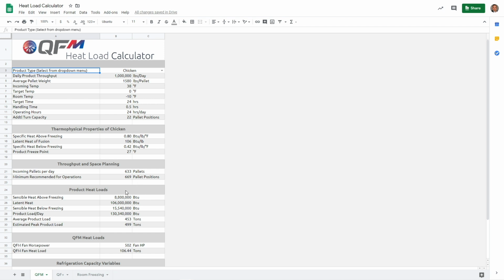We then look at the product heat load. So we have the sensible heat above freezing at 8.8 million BTUs. Our latent heat, 106 million BTUs. Our sensible heat below freezing, 15.54 million BTUs, totaling 130,340,000 BTUs for the process. We then divide that by 12,000 and by 24 hours, and it nets us 453 tons.